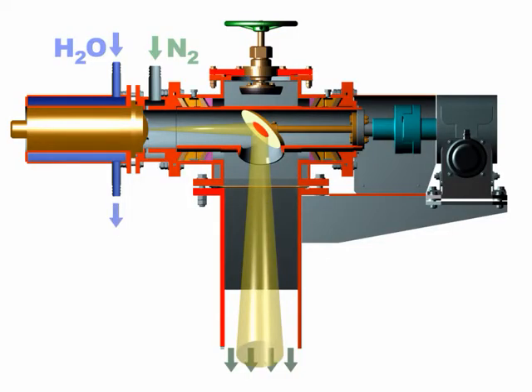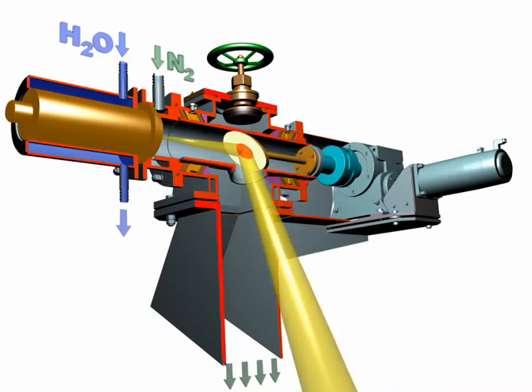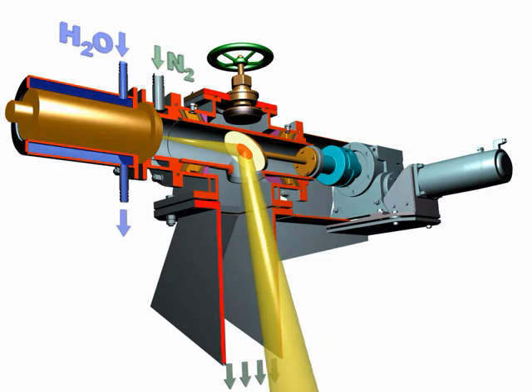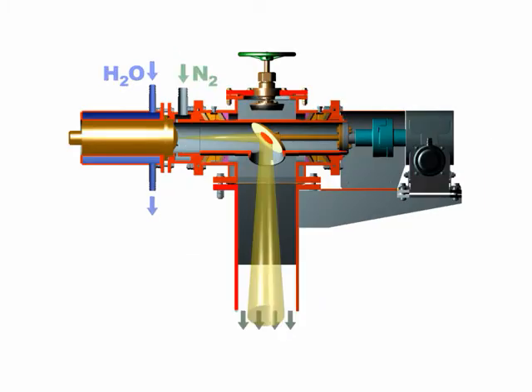Design. The profile meter design is based on the setup, the salient features of which are radar and reflector with its actuator. The system makes it possible to direct an extra high frequency beam through a bore in the slewing body in such a way that individual points on the burden surface could be scanned along the blast furnace radius from periphery to the center. A water cooling jacket cools the radar. To isolate the aggressive medium in the blast furnace from contacts with the reflector, the latter is blown over by nitrogen.